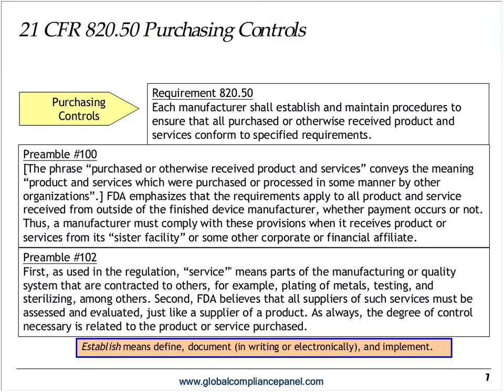So 21 CFR 820.50 is purchasing controls. And so what I've done up here is cited the requirement, and it says that each manufacturer shall establish and maintain procedures to ensure that all purchased or otherwise received product, and we're going to define what that means, or services conform to specified requirements.